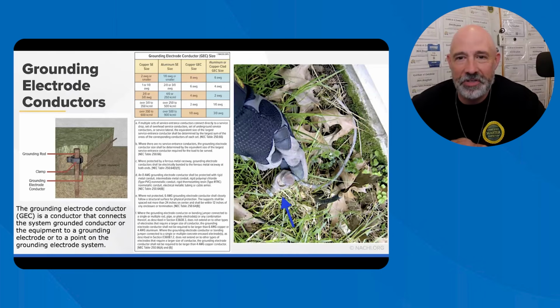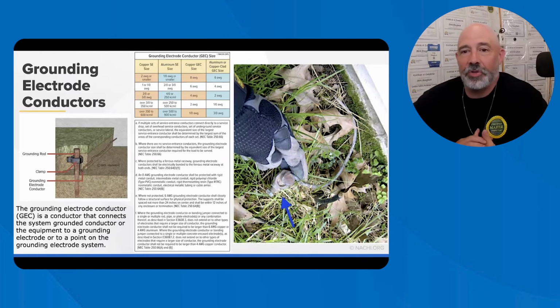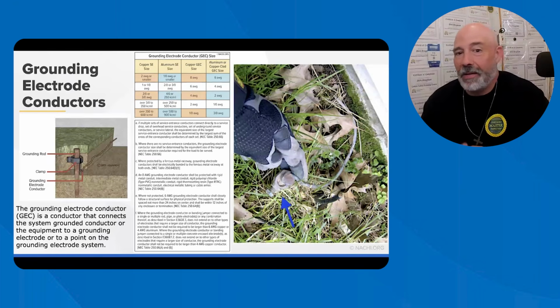Grounding electrode conductors, which is the GEC. The grounding electrode conductor connects the electrical system to the ground electrode. The GEC is typically made of copper or aluminum and normally does not carry current except during a fault. And that's exactly what the grounding wire is supposed to do.